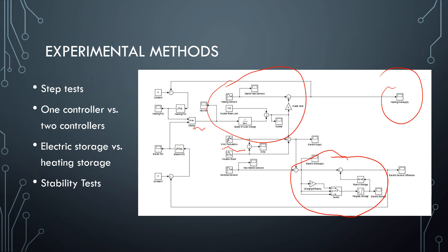We tried a variety of different methods. We tried one controller versus two controllers to control the electric and the heating side of things. We also tried adding both electrical storage and heating storage in one scenario, and we did stability tests to see the outer limits of how far we could push the PIDs.